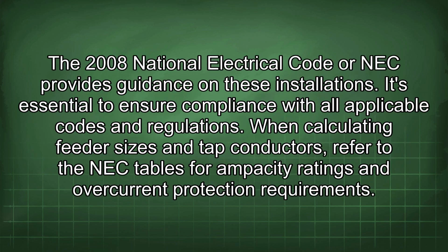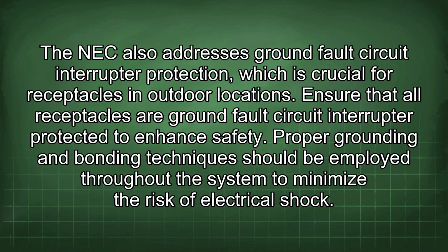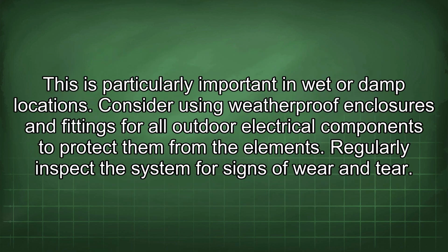The 2008 National Electrical Code, or NEC, provides guidance on these installations. It's essential to ensure compliance with all applicable codes and regulations. When calculating feeder sizes and tap conductors, refer to the NEC tables for ampacity ratings and overcurrent protection requirements. The NEC also addresses ground fault circuit interrupter protection, which is crucial for receptacles in outdoor locations. Ensure that all receptacles are ground fault circuit interrupter protected to enhance safety. Proper grounding and bonding techniques should be employed throughout the system to minimize the risk of electrical shock. This is particularly important in wet or damp locations.